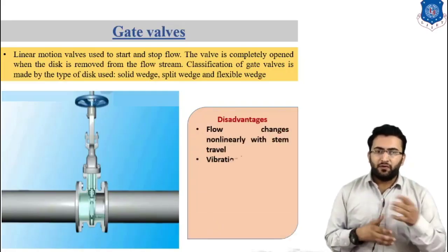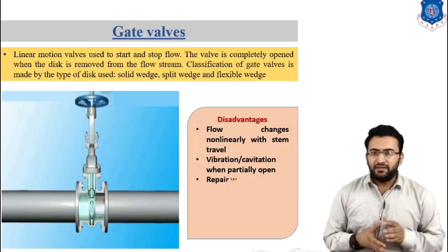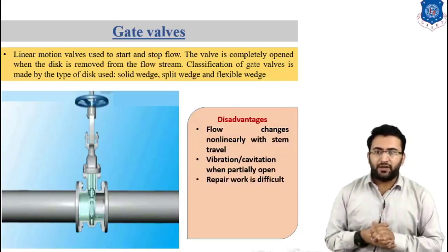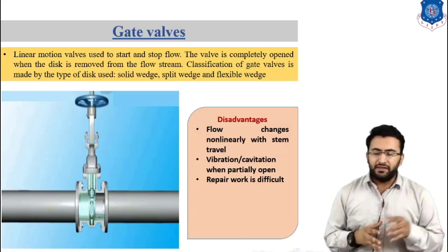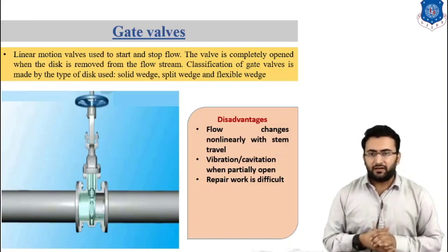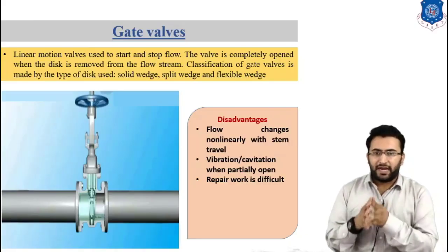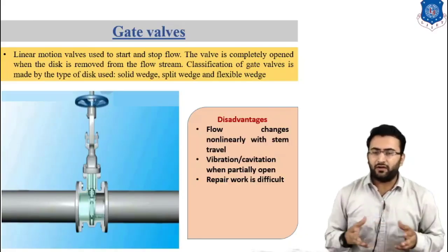Gate valve flow changes non-linearly with stem travel. It vibrates and cavitates when partially open, and repair work is difficult with gate valve. So this is all about the advantages and disadvantages of gate valve.